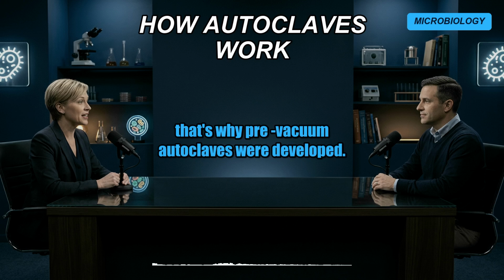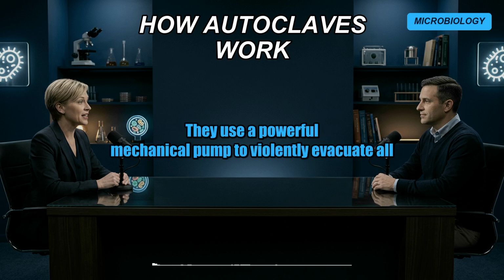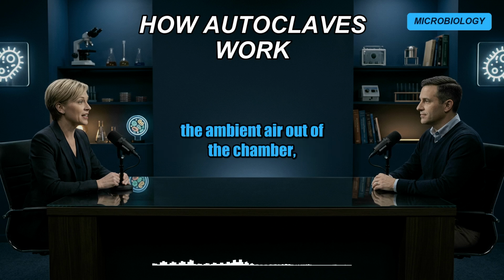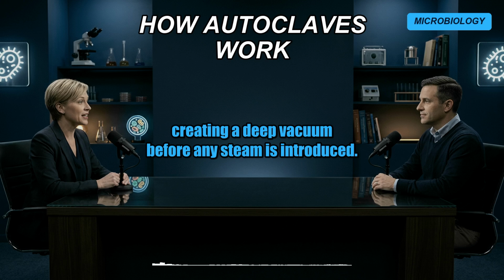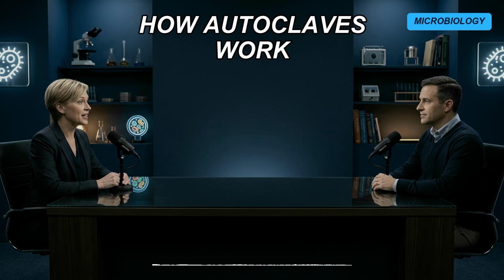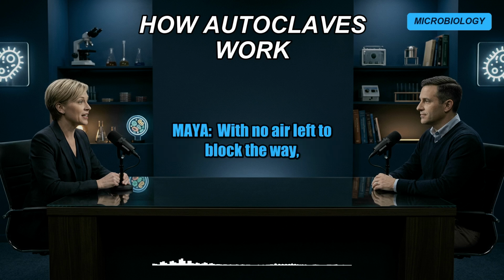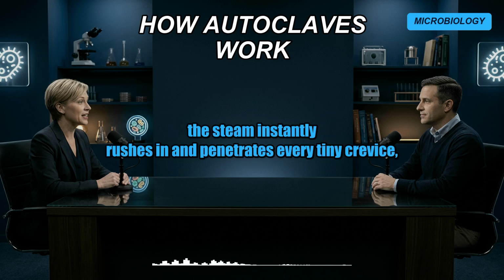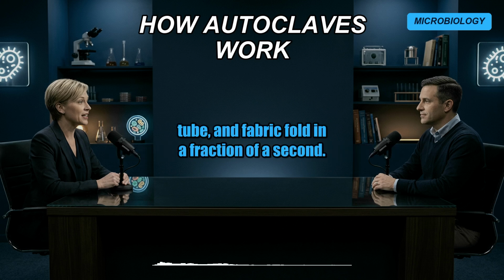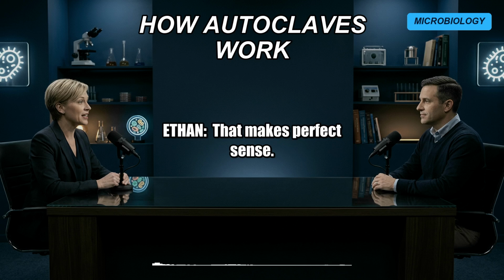Yes, that's why pre-vacuum autoclaves were developed. They use a powerful mechanical pump to violently evacuate all the ambient air out of the chamber, creating a deep vacuum before any steam is introduced. Well, that's smart. With no air left to block the way, the steam instantly rushes in and penetrates every tiny crevice, tube, and fabric fold in a fraction of a second. That makes perfect sense.